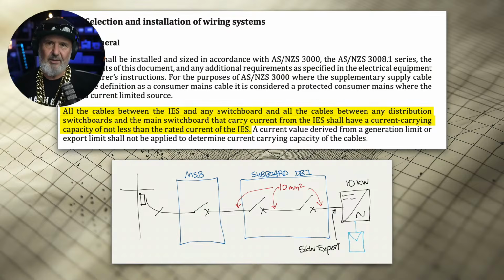Now, when it comes down to billing, it probably doesn't make any difference because it's a momentary event, and so you won't actually see any more export being credited to you, but the cables may well experience it. So if you've got an inverter with a 10 kilowatt output, you need to rate the cables for that.